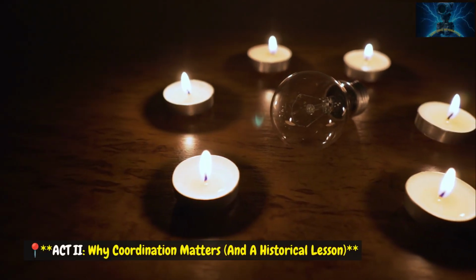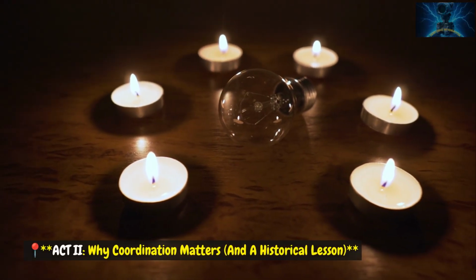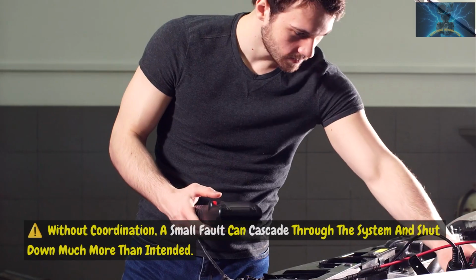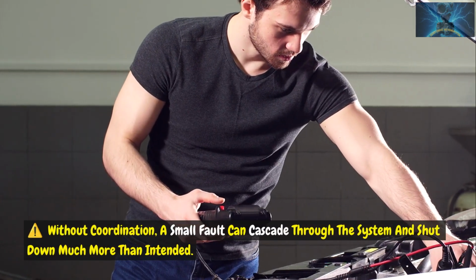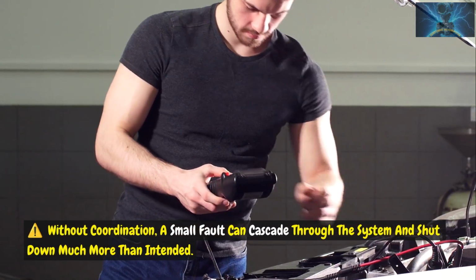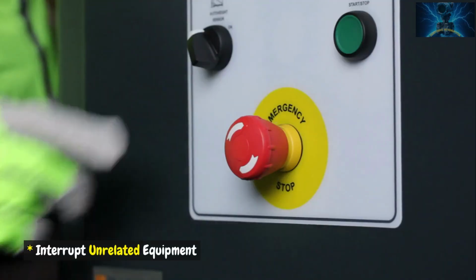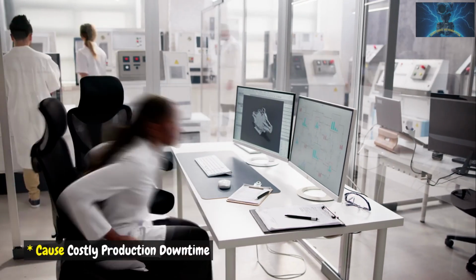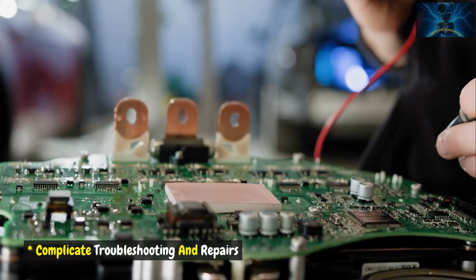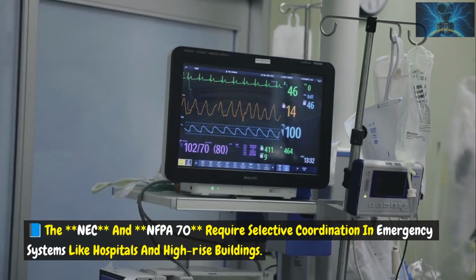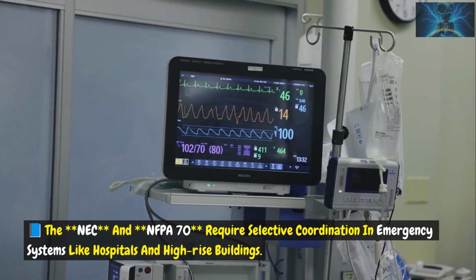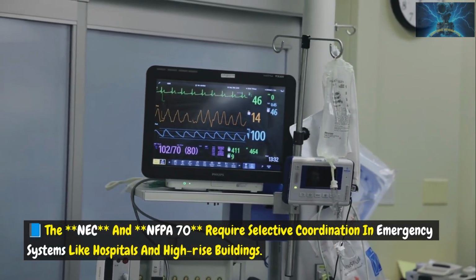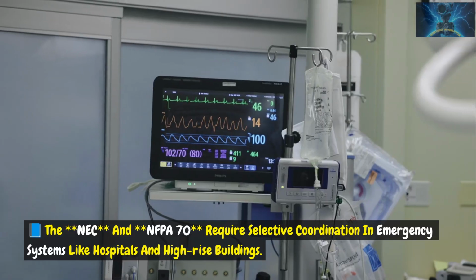Act 2. Why coordination matters, and a historical lesson. Without coordination, a small fault can cascade through the system and shut down much more than intended. This can interrupt unrelated equipment, cause costly production downtime, and complicate troubleshooting and repairs. The NEC and NFPA 70 require selective coordination in emergency systems like hospitals and high-rise buildings.